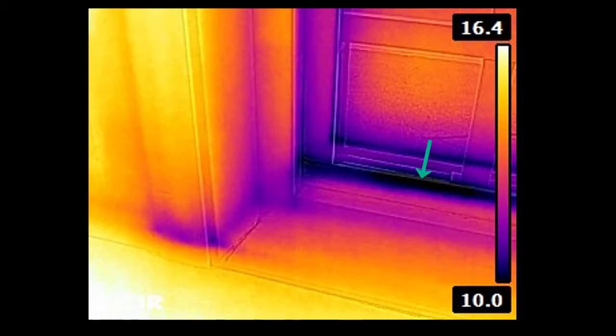So not unexpected, there is condensation on the window. Looking at the infrared image, you can see there's air leakage around the trim. There are black zones or cold zones on the window, indicating the window is not performing very well and not keeping the temperature warm on the window frame.